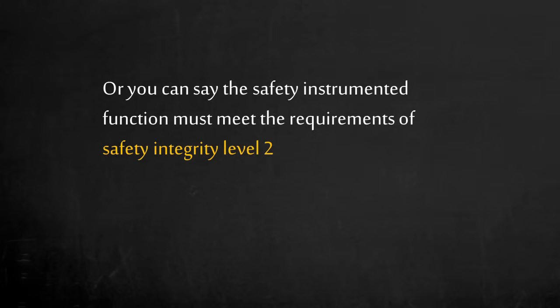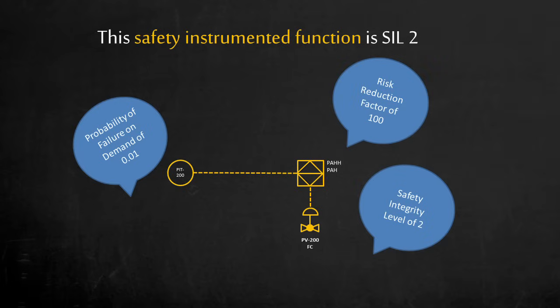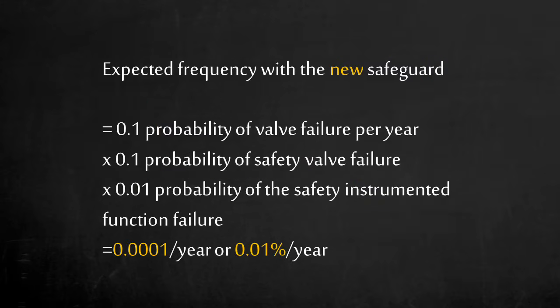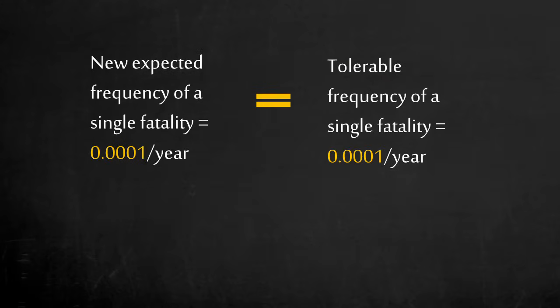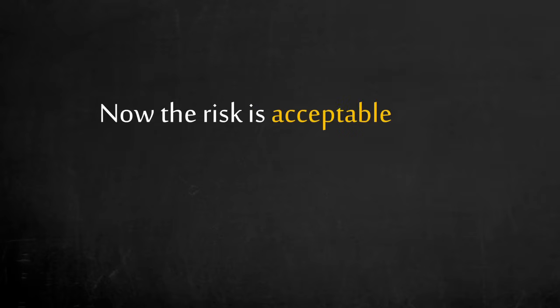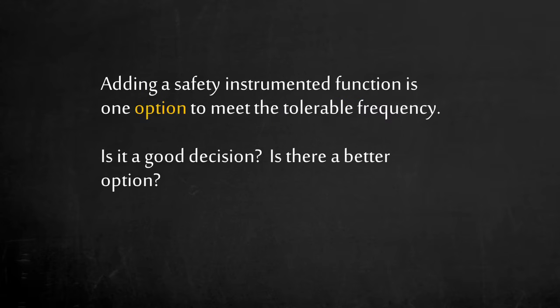We'll talk more about safety integrity level in another course. The combination of the sensor, logic solver, and final element meets the requirements of Safety Integrity Level 2. Now we calculate the new expected frequency of the system. The final result is 0.01% chance per year — the likelihood of the vessel overpressuring is within our tolerable frequency, and we can accept the risk. A safety instrumented function is one of the many ways to meet the tolerable frequency. This option requires adding hardware, but also requires operation to maintain this safety function. Can you think of any other way to lower the likelihood of a fatality?